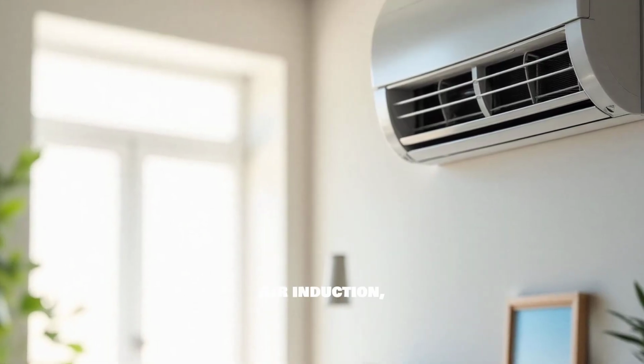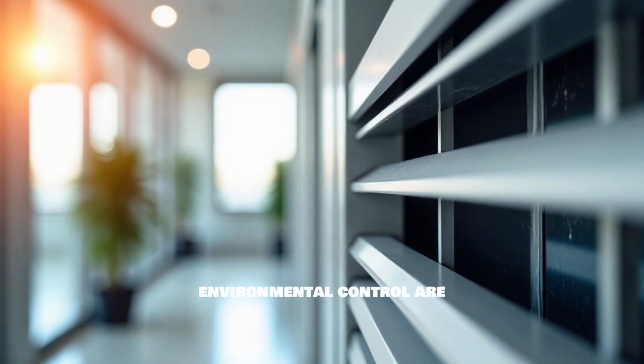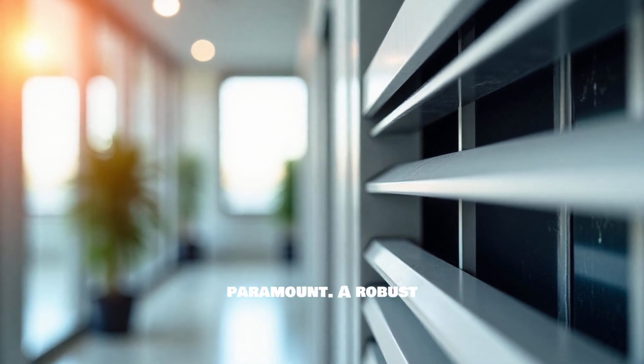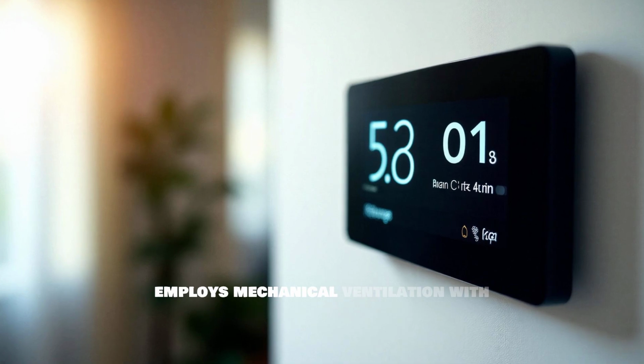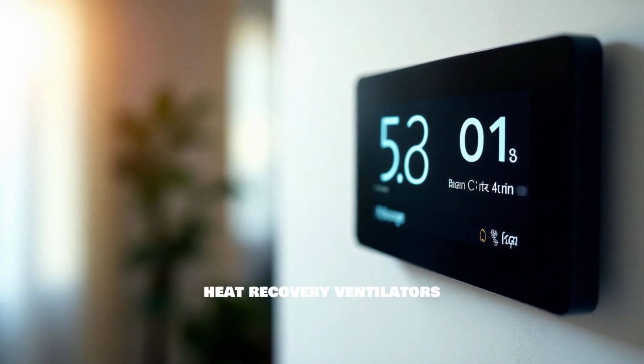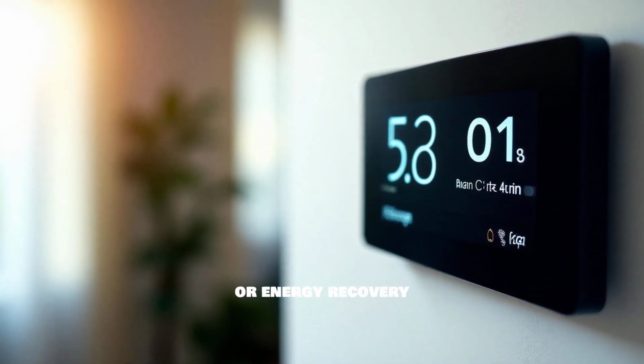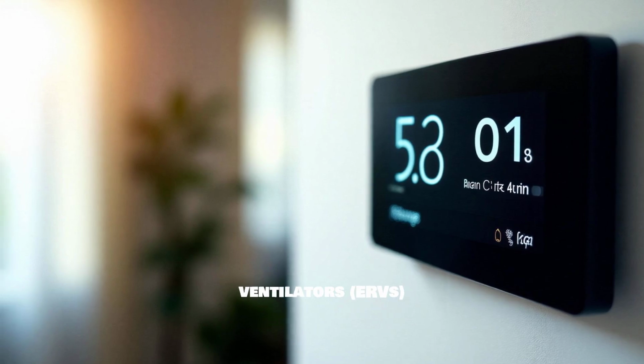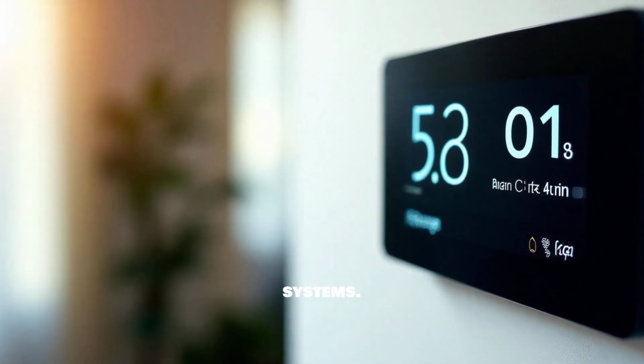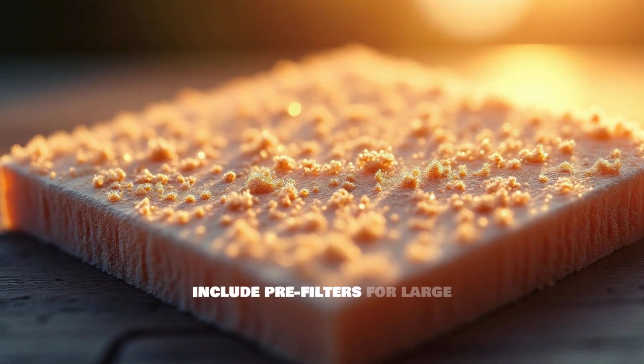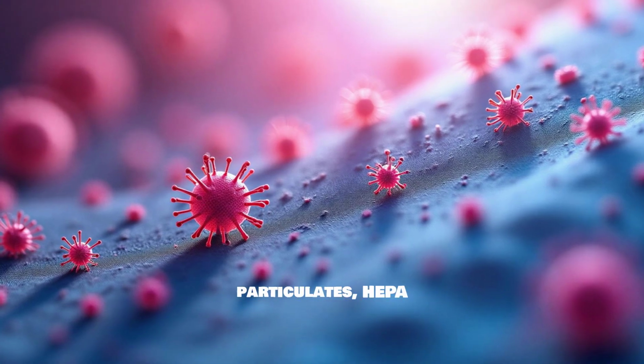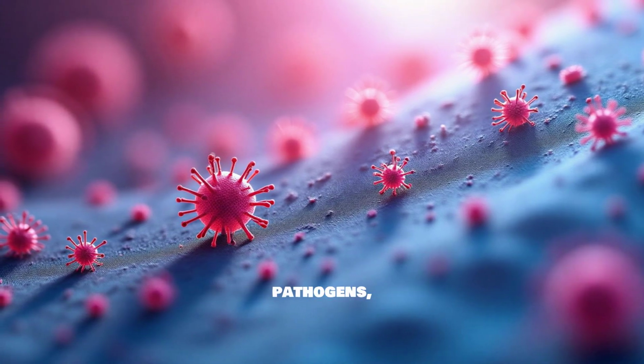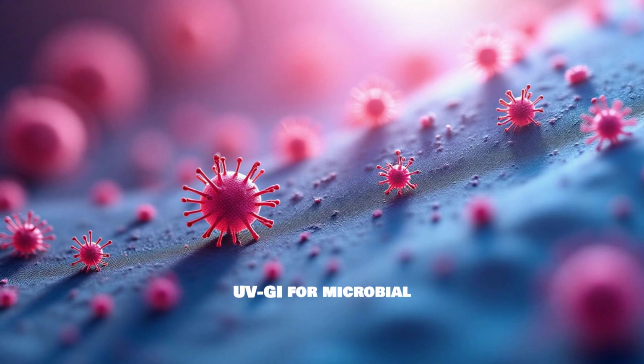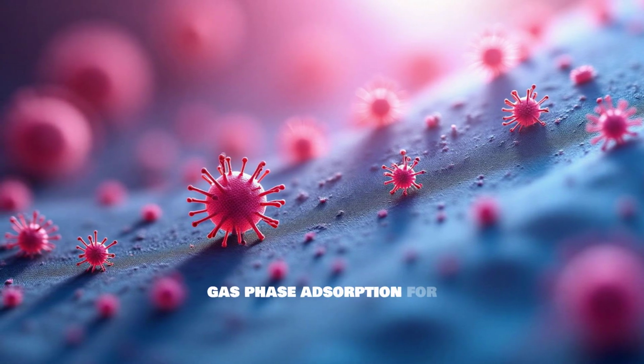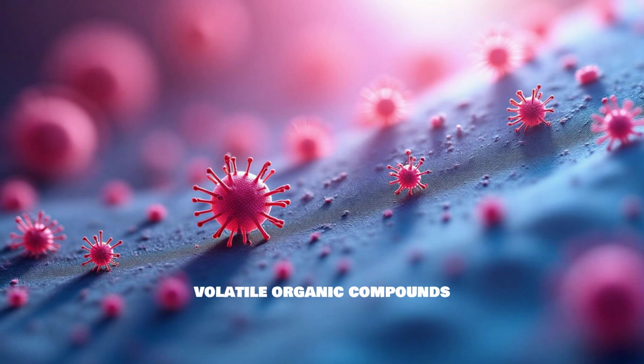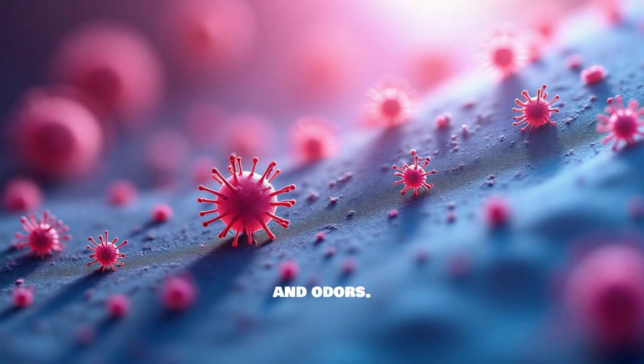Air induction, filtration, and environmental control are paramount. A robust ventilation strategy employs mechanical ventilation with heat recovery ventilators, HRVs, or energy recovery ventilators, ERVs, and demand-controlled systems. Filtration stages include pre-filters for large particulates, HEPA filters for fine particles and pathogens, UVGI for microbial inactivation, and gas phase adsorption for volatile organic compounds, VOCs, and odors.